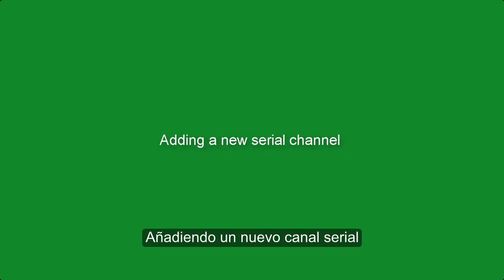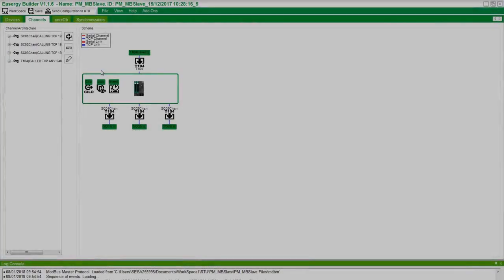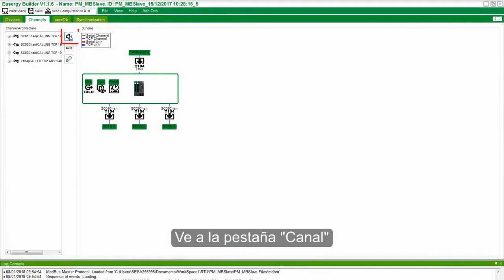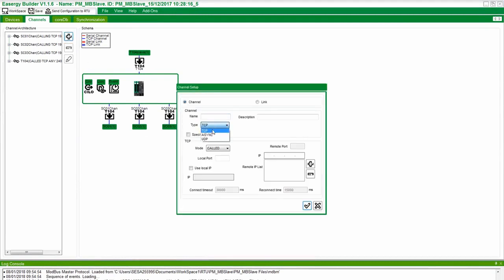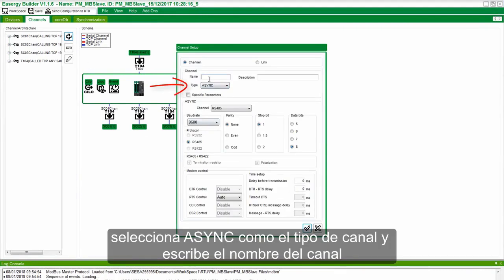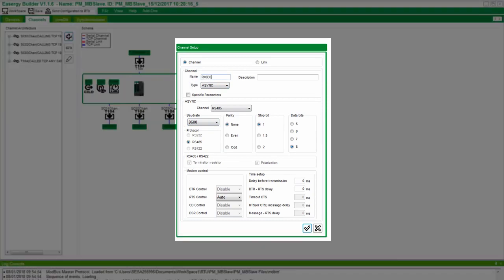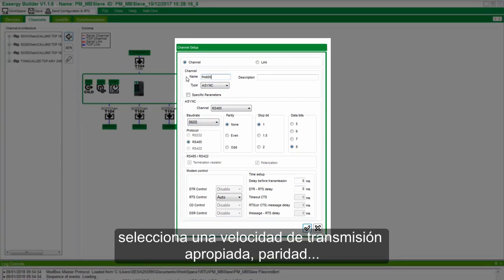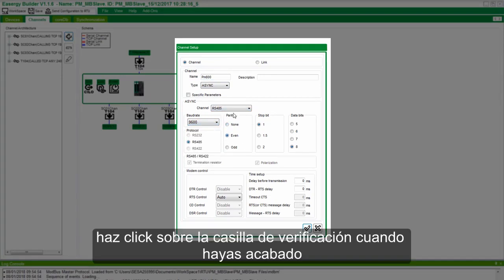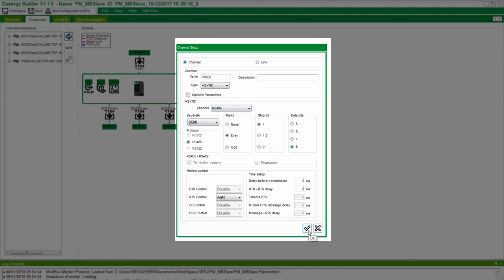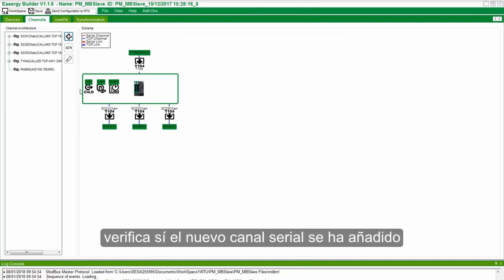Adding a New Serial Channel. Go to the Channels tab and click on the plus sign to add a new channel. Choose Channel Type as Async and enter the channel name. Choose the appropriate Baud Rate, Parity, Stop Bit, and Databits. Click on the checkbox when done. Verify that the serial channel has been added.